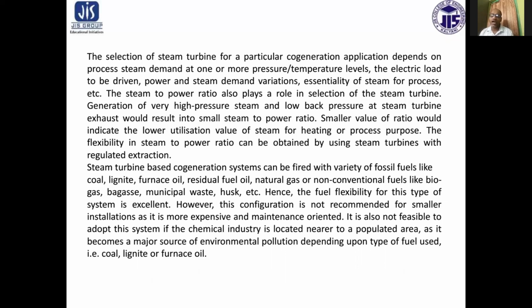Generation of very high pressure steam and low back pressure at steam turbine exhaust would result in a small steam to power ratio. A smaller value of the ratio would indicate a lower utilization value of steam for heating or process purposes. The flexibility in steam to power ratio can be obtained by using a steam turbine with regulated extraction.